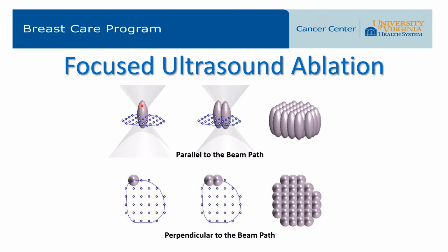Here, that sonication zone is depicted from the side. As you can see, it's cigar-shaped, and we can control the size of these sonication zones to a certain degree. Typically, they're between 5 and 8 millimeters in height and 3 to 5 millimeters in width. It's a pretty small area. So in order to target a tumor, which is going to have a much higher volume than that, we need to put together a treatment plan.